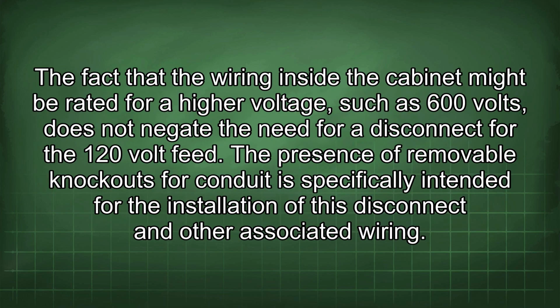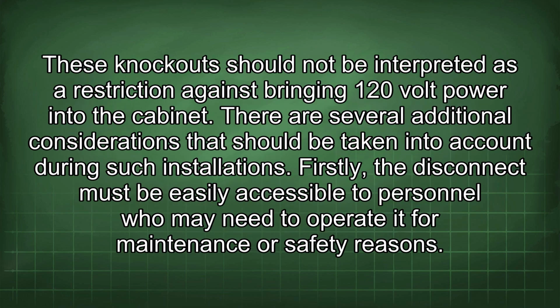The fact that the wiring inside the cabinet might be rated for a higher voltage, such as 600 volts, does not negate the need for a disconnect for the 120 volt feed. The presence of removable knockouts for conduit is specifically intended for the installation of this disconnect and other associated wiring. These knockouts should not be interpreted as a restriction against bringing 120 volt power into the cabinet. There are several additional considerations that should be taken into account during such installations.